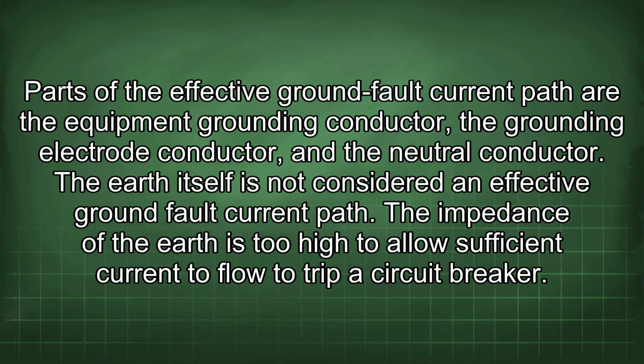Parts of the effective ground fault current path are the equipment grounding conductor, the grounding electrode conductor, and the neutral conductor. The earth itself is not considered an effective ground fault current path. The impedance of the earth is too high to allow sufficient current to flow to trip a circuit breaker.